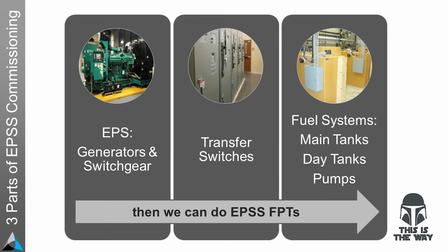To be able to test the entire emergency power system, we need to have the EPS, the generator itself, generators and switchgear. That has to be done and tested, including load bank tests. The transfer switches need to be done, tested, set up, programmed, all of that. And the fuel system needs to be done and tested, pumps and all of that.